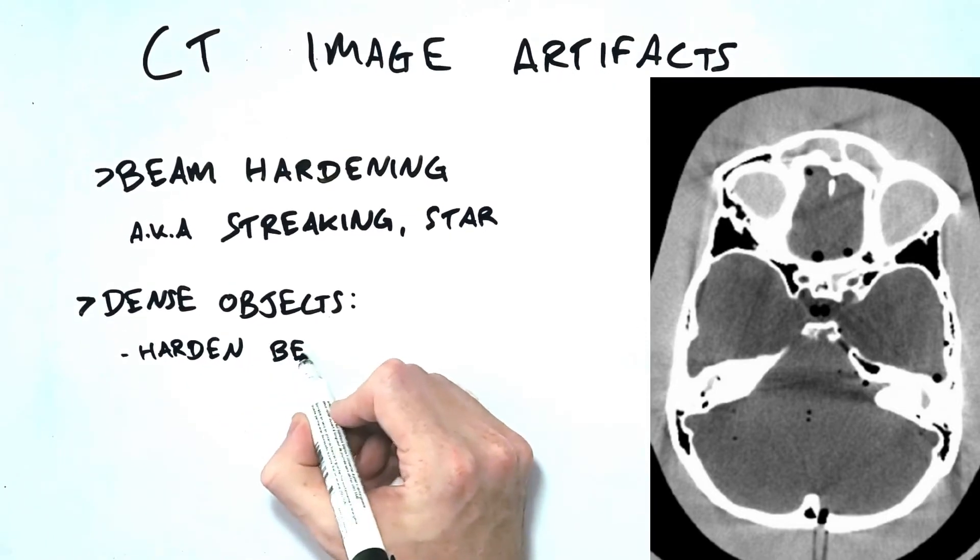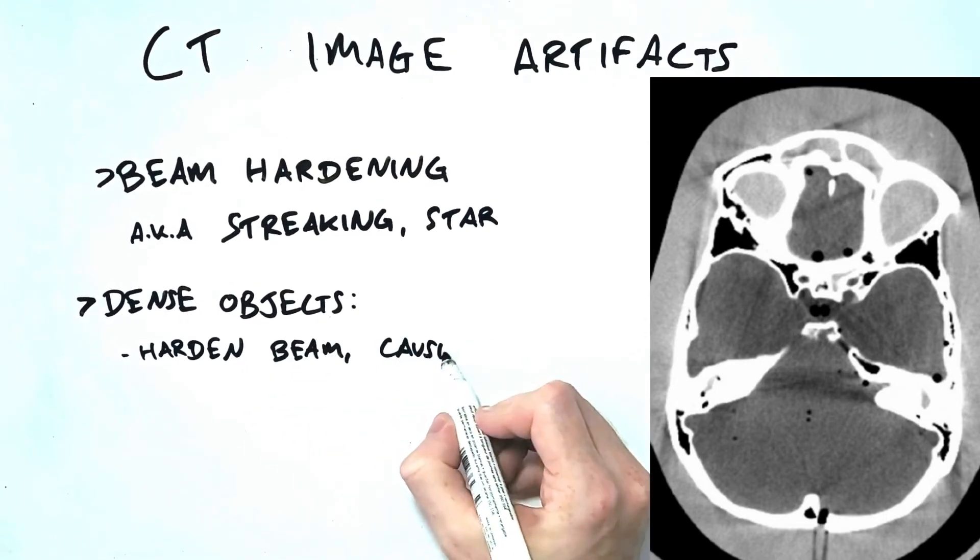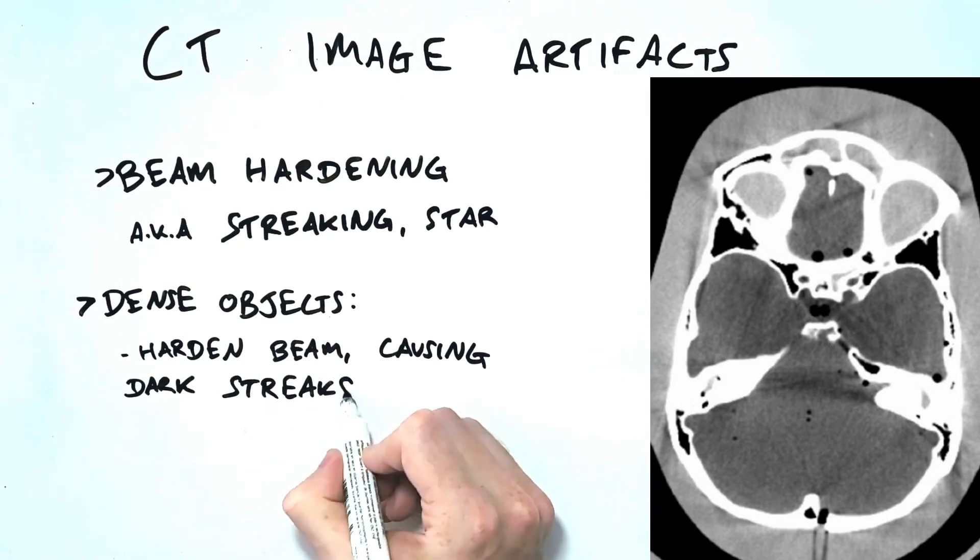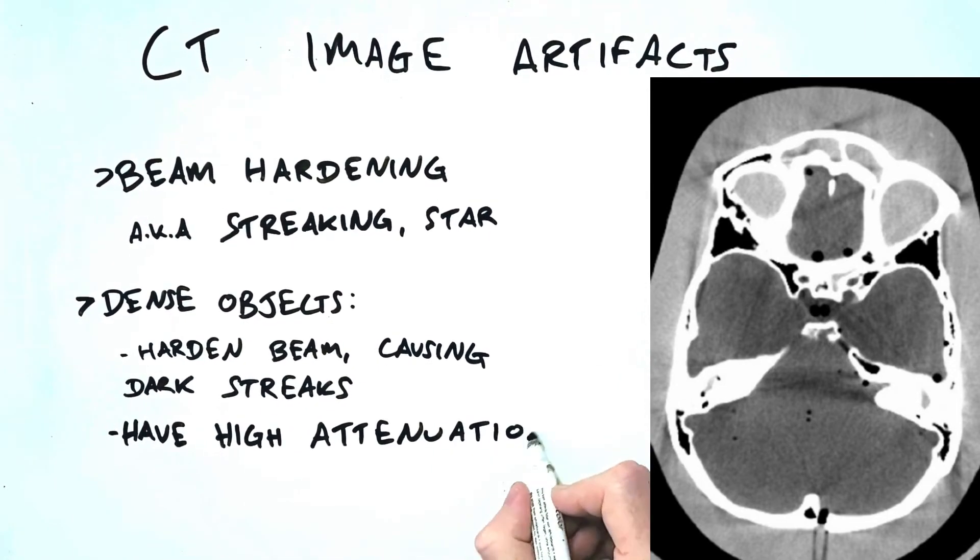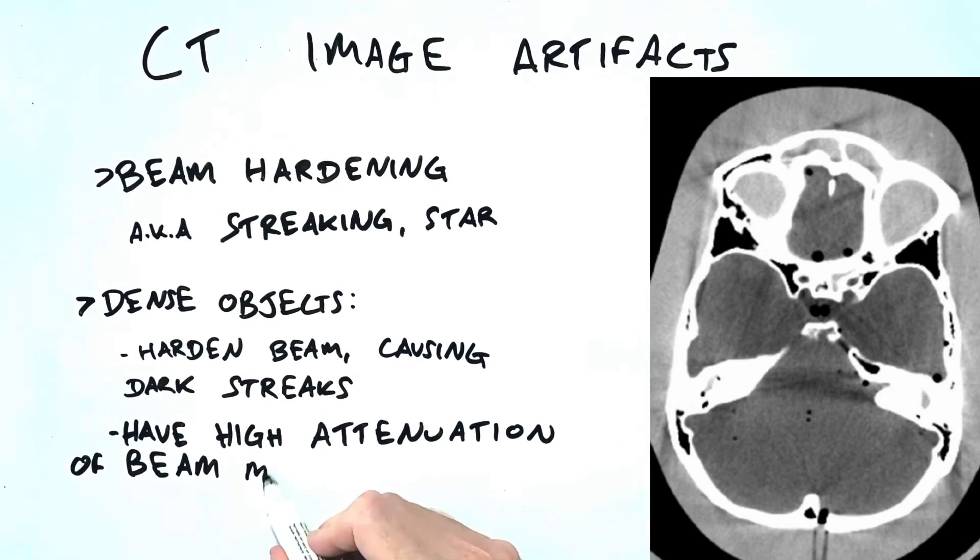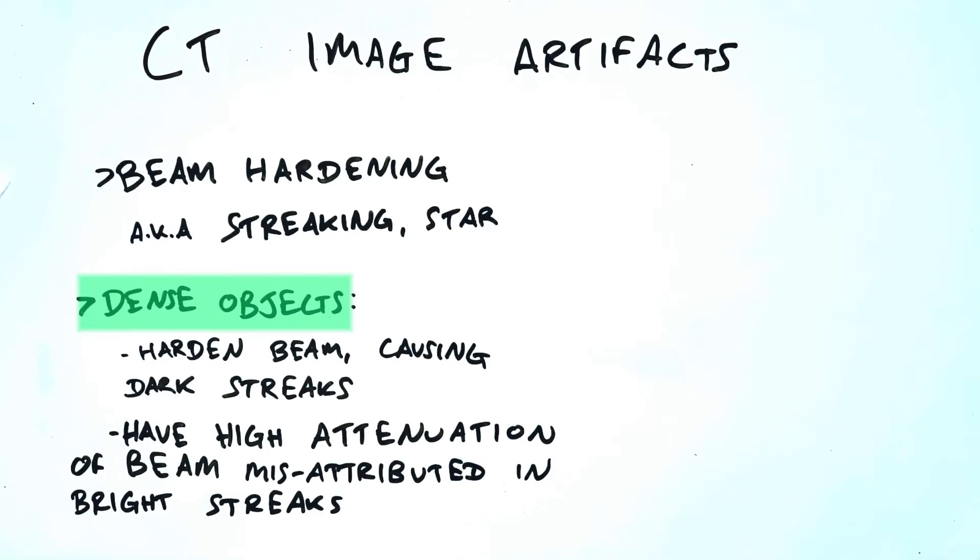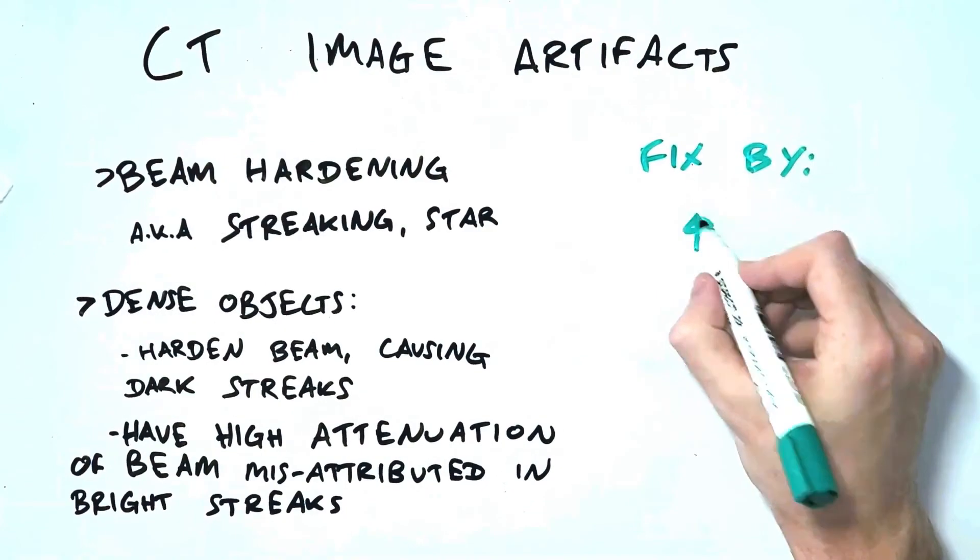The dark areas are the result of the beam having a higher average energy when passing through in that direction because the low-energy photons have all been attenuated by the dense structure. The bright areas are the result of some of that very high amount of attenuation being misattributed to nearby areas along the same projection pathway. If you want a simple answer as to why this happens, it's basically because we are scanning very dense structures which are beyond the optimal range of the scanner's capabilities.